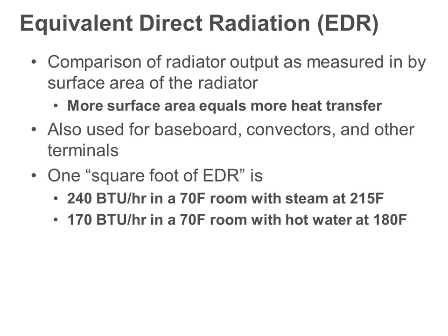certain amount of heat. Now, we talk about steam here, okay? But for 215 degree steam, which is about 1 to 2 psi at most, you're going to get 240 BTUs off of that 1 square foot of that radiator. When we're dealing with water, that number drops dramatically because we've got to remember water, we're looking at 180 degree supply water temperature. At that point, we get about 170 BTUs an hour. Okay, so that's the number we always remember. At 180 degrees, we get 170. Were there systems out there running 190, 200 degrees? Yes. Okay, that's not the typical.